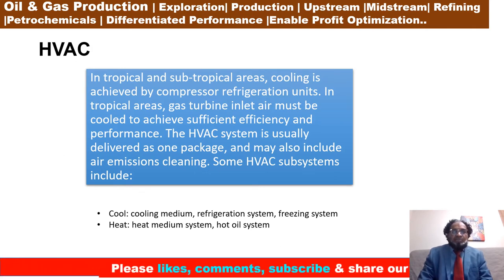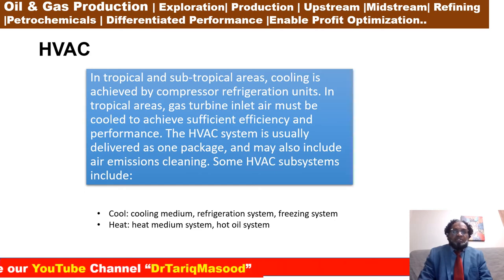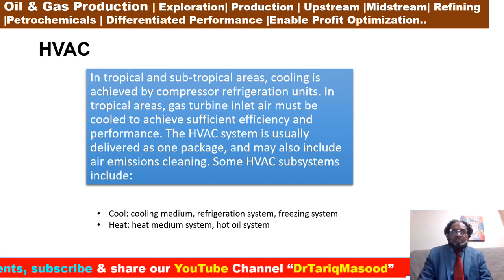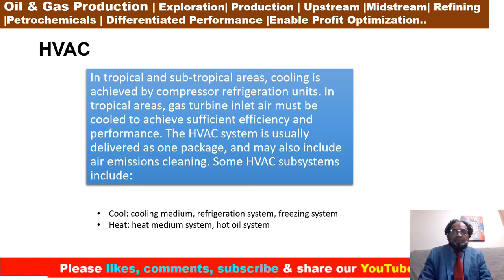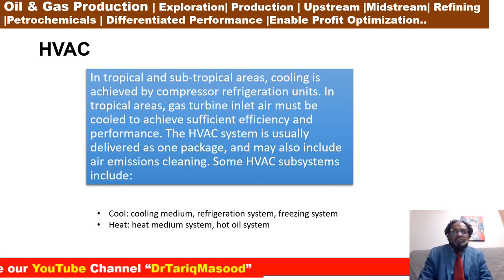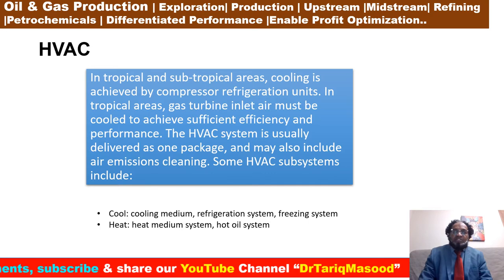The HVAC system is usually delivered as one package and may also include an air emissions cleaning or emission control system, and a continuous emission monitoring system as well. Okay, some HVAC subsystems include: first, cooling, a cooling medium refrigeration system and a freezing system; number two, heating, heat medium systems and hot system, etc. One function is to provide air to the equipment rooms that are kept under a positive pressure. This prevents a potential influx of explosive gas in case of a leak.